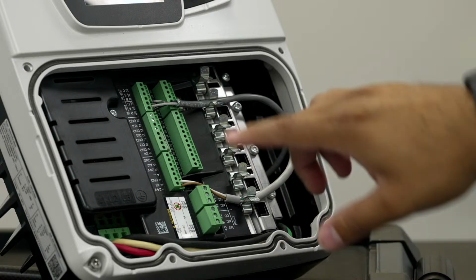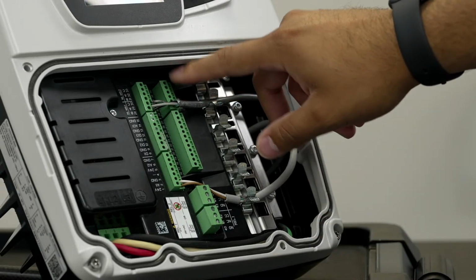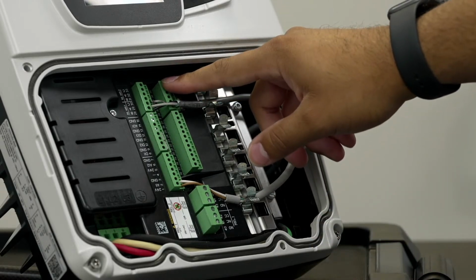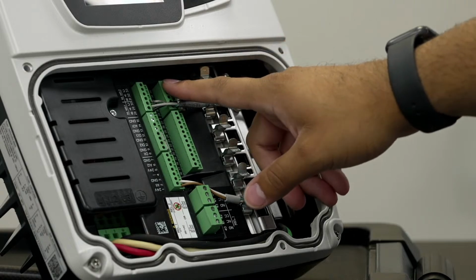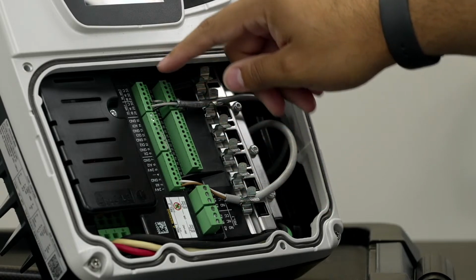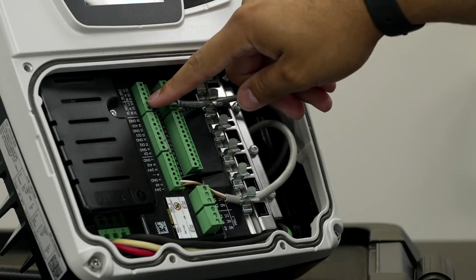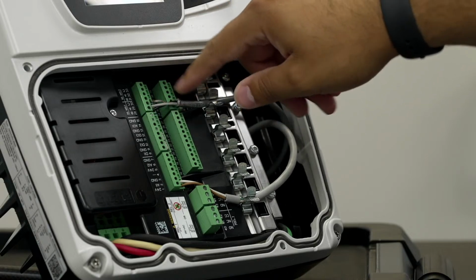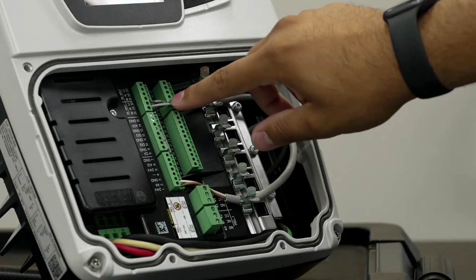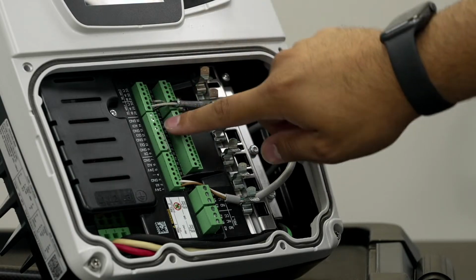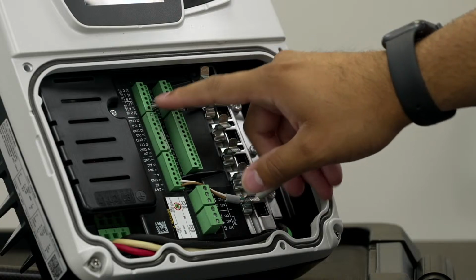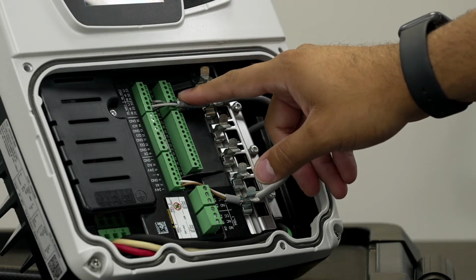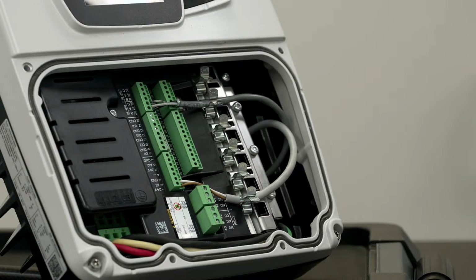And on top of that, we have a secondary bank here. Once again, in a lot of different VFDs, if there was more than 2 pumps in the system, you would need wiring coming in from VFD number 1, and then wiring going out to the next VFD, and you would have to cram multiple wires into these small banks. We have an additional port. So basically we have incoming and outgoing wiring available. Just a ton of different RS-485 communication terminals available for you, to keep that ease of wiring nice and simple for users out in the field.